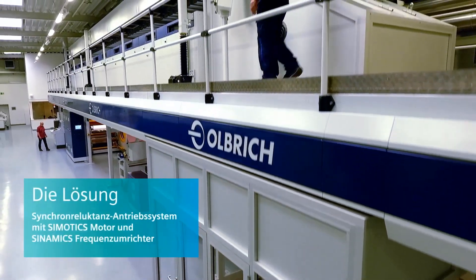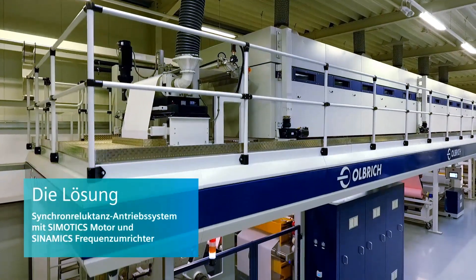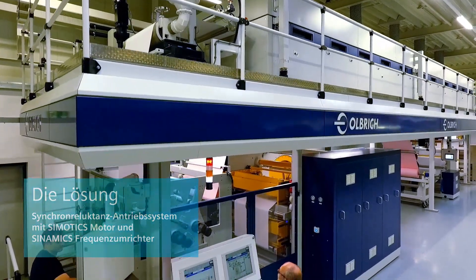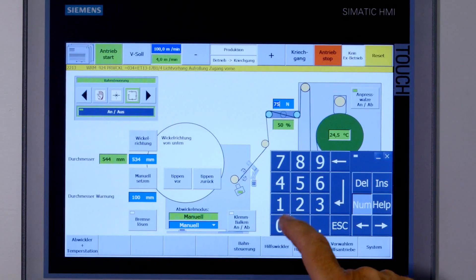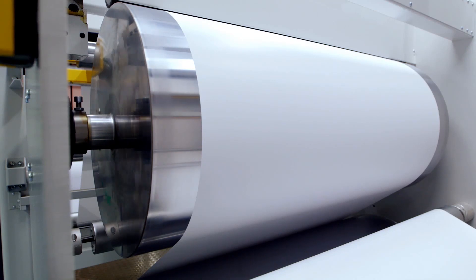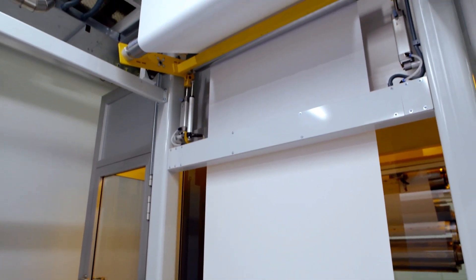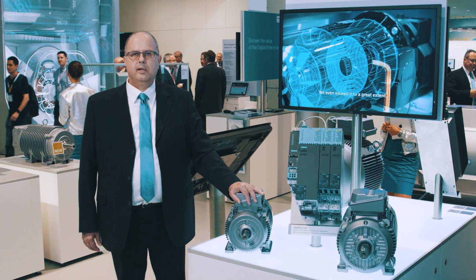SIMOTICS Synchronous Reluctance Motors together with the high-performance SINAMICS G120 Converter System were selected as a solution. The reluctance drive system has proven itself with its high speed precision, and production processes can be optimally controlled with encoderless vector control. Further, a high system efficiency exceeding IES-2, along with motor efficiencies exceeding or comparable to IE-4, have resulted in reduced energy consumption.